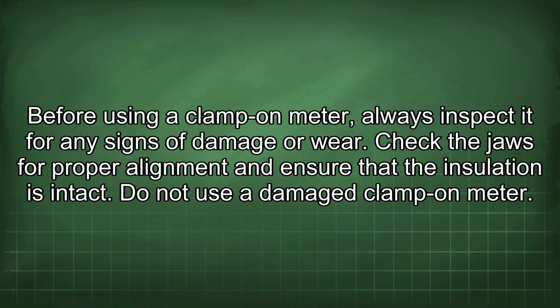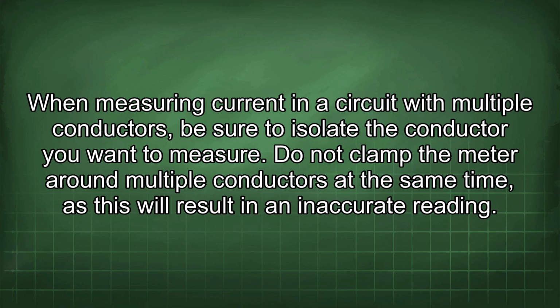Before using a clamp-on meter, always inspect it for any signs of damage or wear. Check the jaws for proper alignment and ensure that the insulation is intact. Do not use a damaged clamp-on meter. When measuring current in a circuit with multiple conductors, be sure to isolate the conductor you want to measure. Do not clamp the meter around multiple conductors at the same time, as this will result in an inaccurate reading.